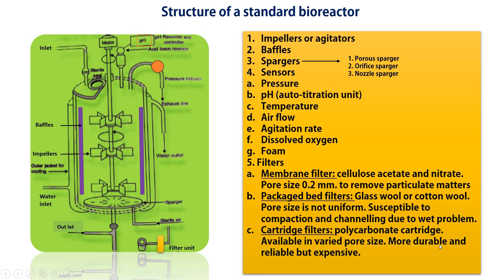It is not utilized recently in high-end bioreactors, because it is susceptible to compaction and channeling due to wet problems. There is every chance of leakage of the media, and that media may come out through the pipeline, come in contact with this glass wool or cotton wool, and make it wet. For that problem, in present days, these filters are not typically used. Instead, they use cartridge filters made of polycarbonate materials, available in varied pore sizes. Depending on our specific requirement, the pore size can be determined, and they are more durable and reliable, but a little bit expensive.